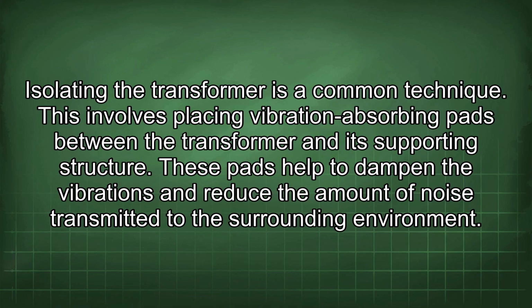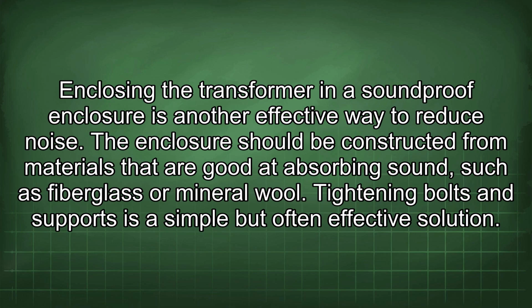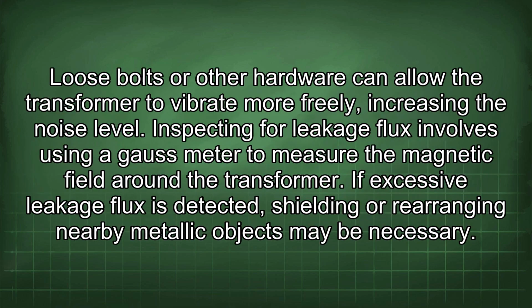Isolating the transformer is a common technique. This involves placing vibration-absorbing pads between the transformer and its supporting structure. These pads help to dampen the vibrations and reduce the amount of noise transmitted to the surrounding environment. Enclosing the transformer in a soundproof enclosure is another effective way to reduce noise. The enclosure should be constructed from materials that are good at absorbing sound, such as fiberglass or mineral wool. Tightening bolts and supports is a simple but often effective solution. Loose bolts or other hardware can allow the transformer to vibrate more freely, increasing the noise level.